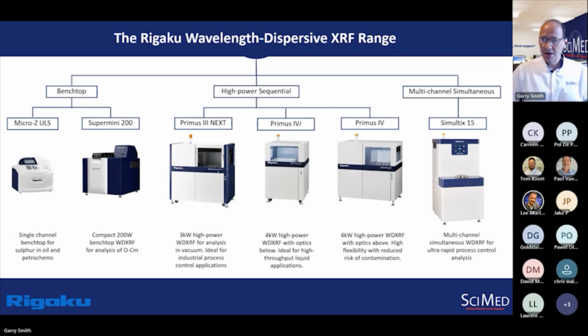So working from left to right, we start with the MicroZ ULS. This is a single-channel benchtop system designed specifically for measurement of sulfur in oil and petrochemicals. This is for compliance with industry standard methods like ASTM D2622, where wavelength dispersive XRF is the stipulated technique, but sulfur is the only element of interest. Next, we have the Super Mini 200. This is a compact benchtop sequential spectrometer with elemental coverage from oxygen right through to curium. It uses a 200-watt X-ray tube, and the advantage of this system is that we get this very wide elemental coverage from a completely self-contained unit, which doesn't need any external services other than power and P10 gas for the detector.